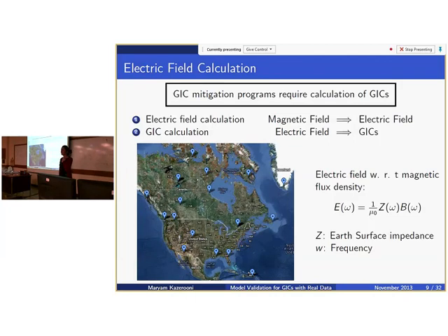One more question. Is there a term like a safety factor? Because if I have a transformer that's not being used very much, and I see 20 amps of DC, it's a really big deal. But what if I have a transformer that's nearly saturated and on the verge of being exploded, and then I get 40 amps? Is there in this study a safety factor or some term you say, okay, a GIC of this level is okay?